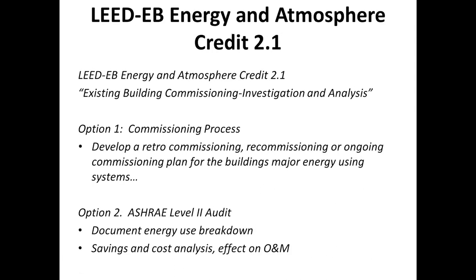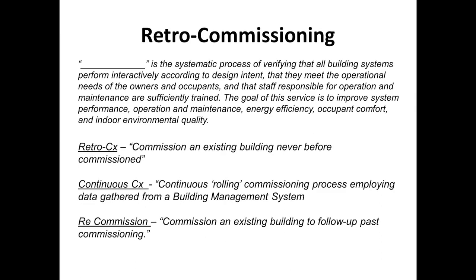And again, just to bring up credit 2.1, since we've defined ASHRAE level 2, there are two options. There's a commissioning process, like I previously stated, that's developing a retro-commissioning plan, moving forward with implementation, and then tracking the energy use. There are different credits for each different phase. So there are more credits on that path, but there's also the ASHRAE level 2 energy audit, which is doing a one-time ASHRAE level 2 energy audit, submitting a report, and showing that there are opportunities other than operation and maintenance that were researched and studied within the building and recommended to the building owners and management.